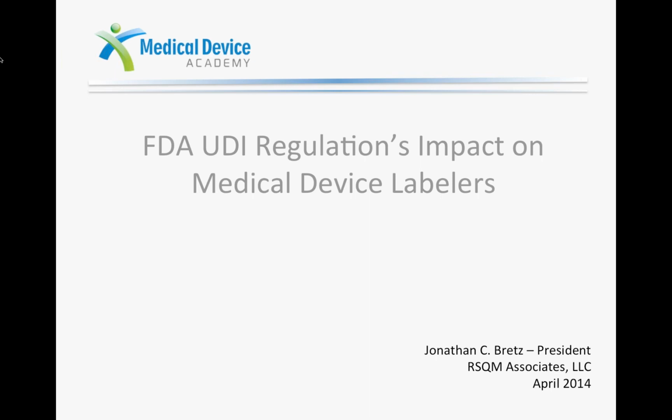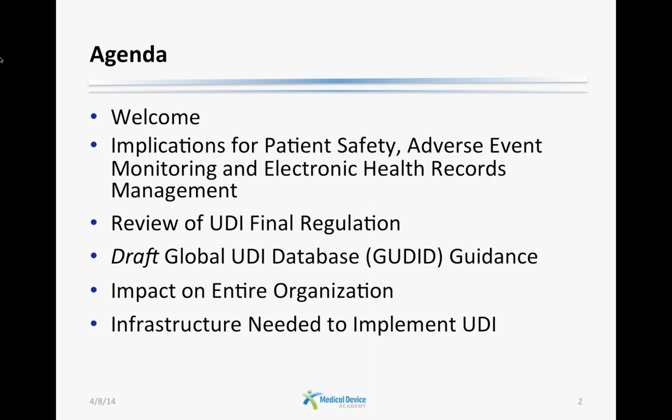There are many different reasons why FDA enacted this new regulation. Most center on post-market surveillance. Specifically, it is looking to improve adverse event reporting and aggregation thereof to identify trends, have more thorough and complete recalls, add device usage to disease-specific registries, include device usage into electronic health records and large population-based data sets, i.e. data claims.